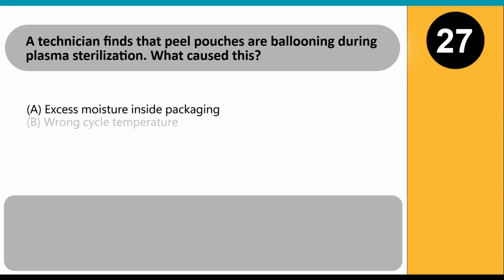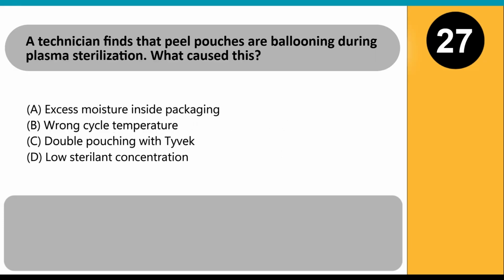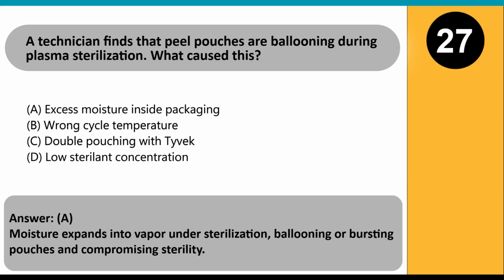A technician finds that peel pouches are ballooning during plasma sterilization. What caused this? A. Excess moisture inside packaging. B. Wrong cycle temperature. C. Double pouching with Tyvek. D. Low sterilant concentration. Answer A. Moisture expands into vapor under sterilization, ballooning or bursting pouches and compromising sterility.